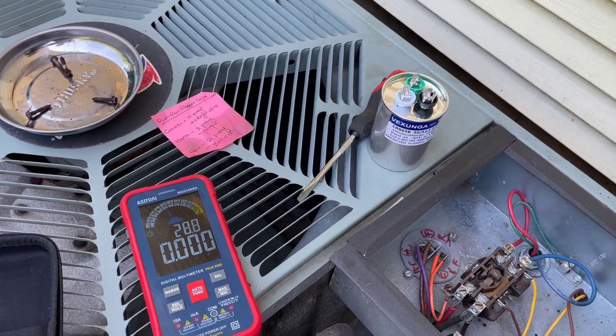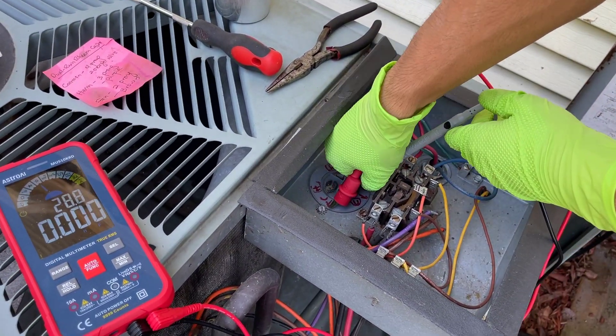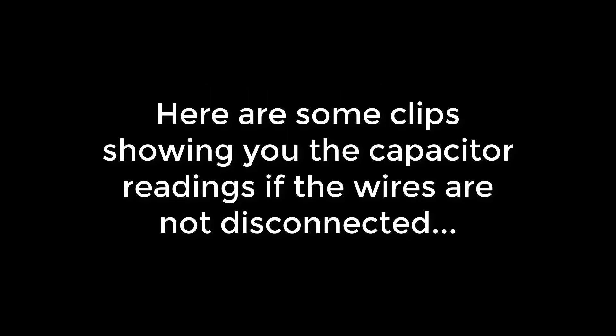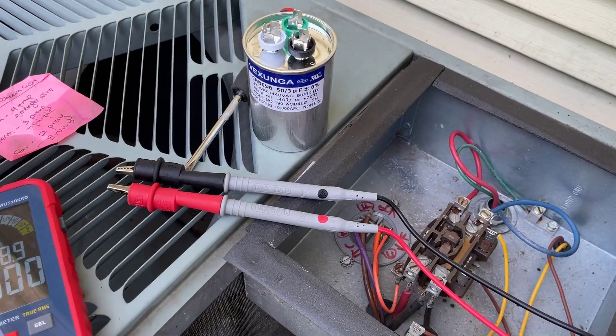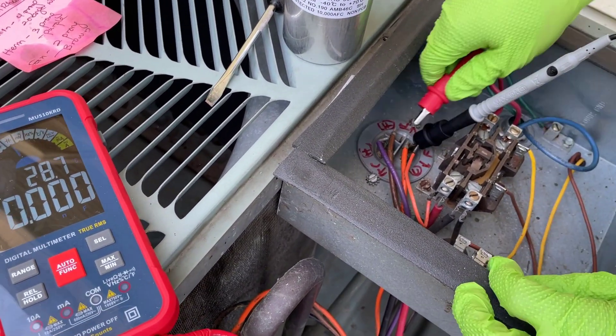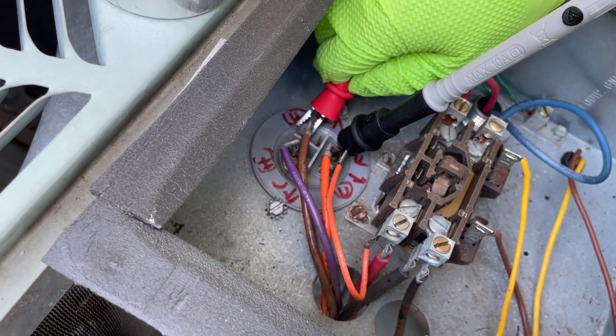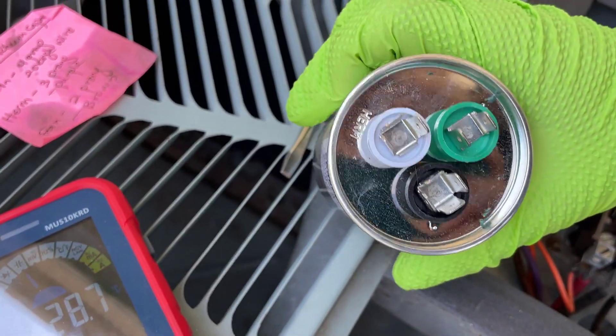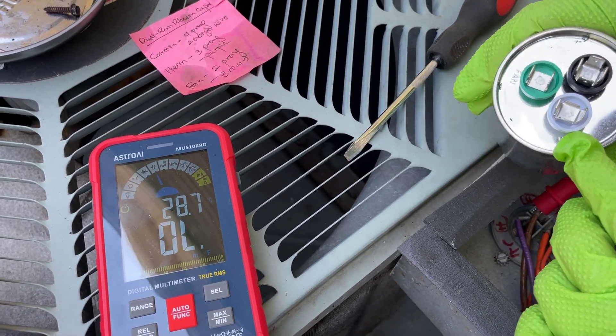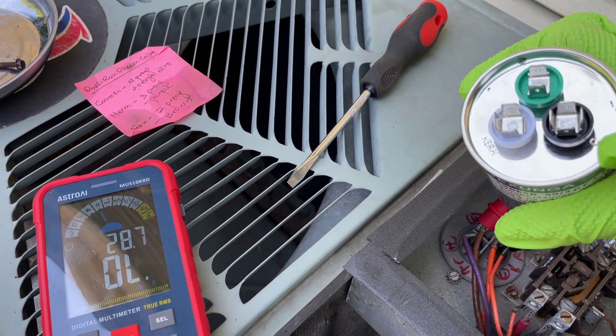That means our capacitor is not up to spec — I meant to say capacitor, not compressor. So we're sure that it's the capacitor that's the issue, and we're going to take it out and replace it with the new one. We're connecting to the fan. You can see this says C, F, and H, which refer to common, hermetic, and fan. The reason they use hermetic is that hermetic means compressor — if they used C for compressor, you'd confuse it with C for common, so they call it hermetic instead.